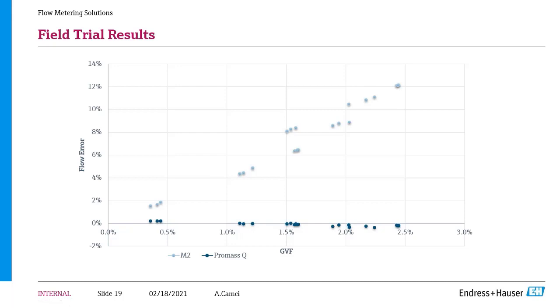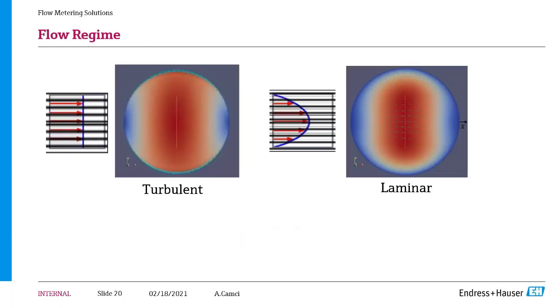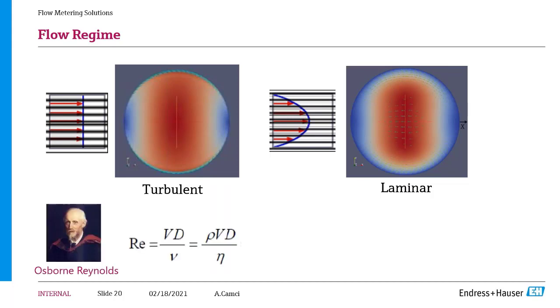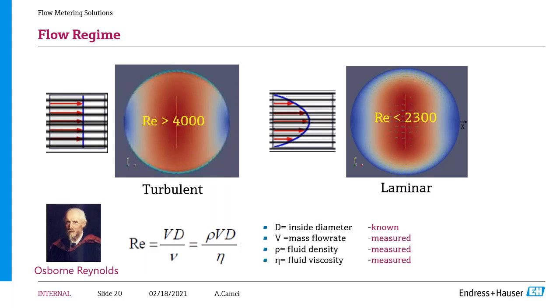And for the second difficulty, which is the flow regime, we speak about turbulent and laminar flows. To define turbulent and laminar flow inside the pipeline, this gentleman, Osborne Reynolds, created a dimensionless number, which we call the Reynolds number today. This number is a formula with some flow and fluid parameters, and by defining the Reynolds number, we can decide if the flow is laminar or turbulent. The equation contains the inside diameter, mass flow rate, fluid density, and fluid viscosity. The last three are measurable parameters by the Coriolis meter, and the inside diameter is known.